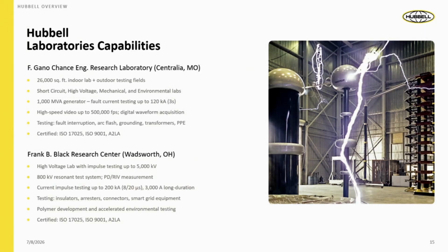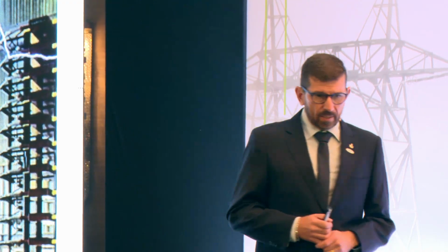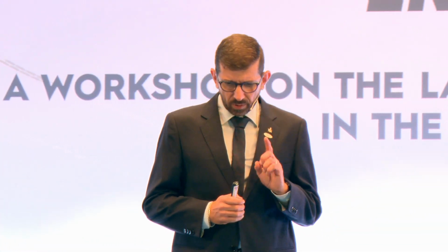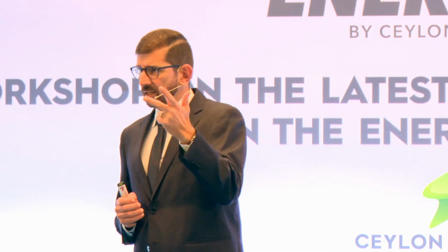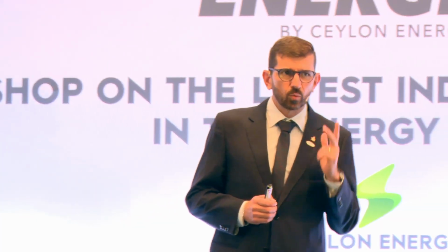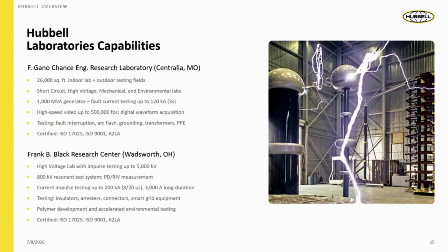We also have Frank Black Research Centers in Wadsworth, Ohio, where we have a lab for testing impulse up to 5,000 kV. This is very important because it's one of only two or three labs in the world where you can do impulse tests, voltage tests, and aging tests at the same time, especially for insulators, arresters, MOV blocks, and other products. Current impulse test up to 200 kA. It's a big advantage and capacity for us to test all of our products and simulate the worst case scenario that can happen on the grid.